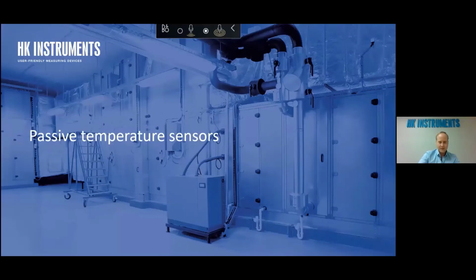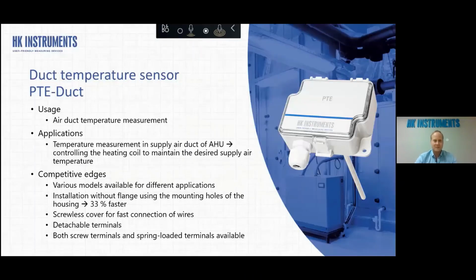So then we have still some more sensors to come up. So this is the passive temperature sensor series. We have those now for air, and here you can see maybe the most commonly used one, the duct sensor. So the applications are the temperature measurement basically from different parts of the air handling unit. For example, supply air. For example, to control the heating coil to maintain the desired supply air temperature.